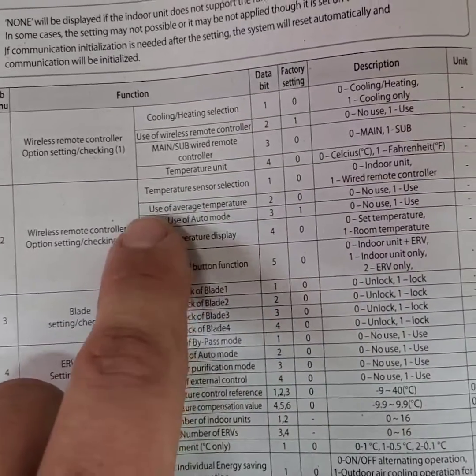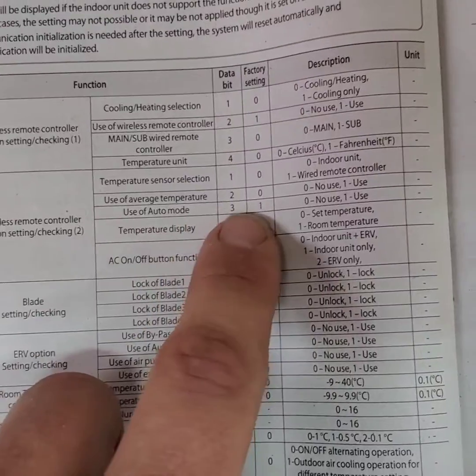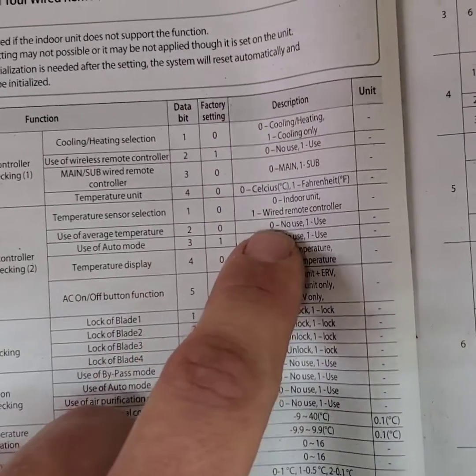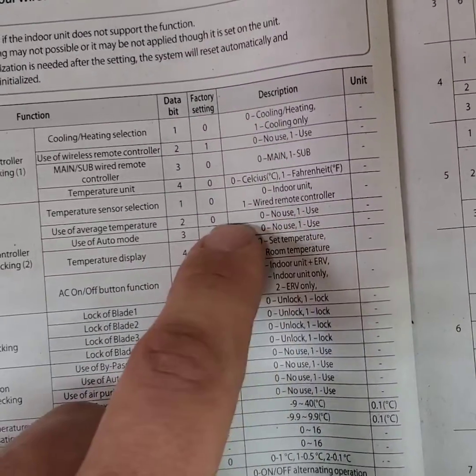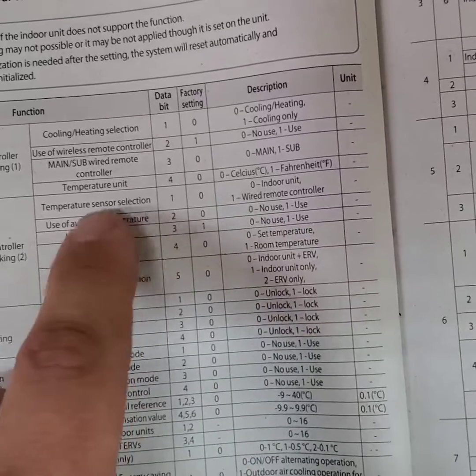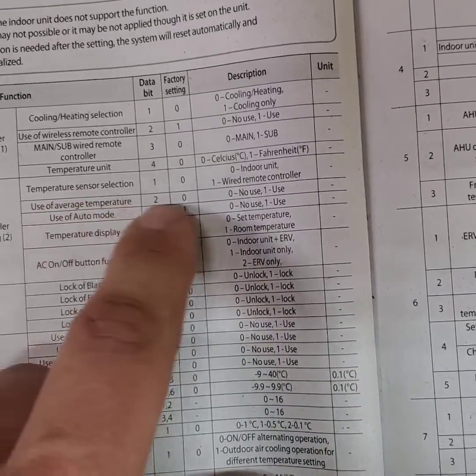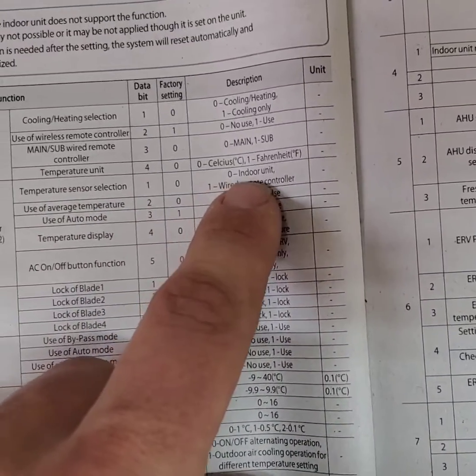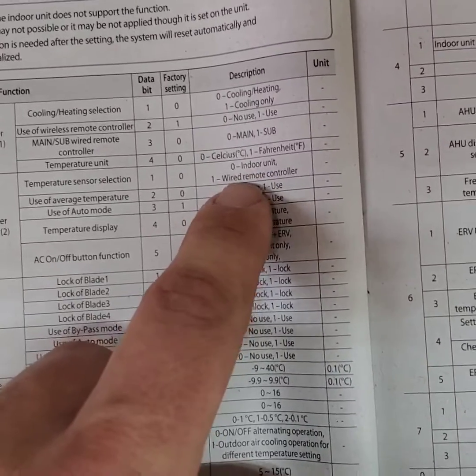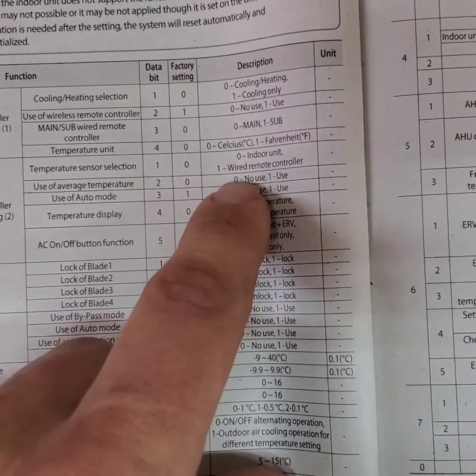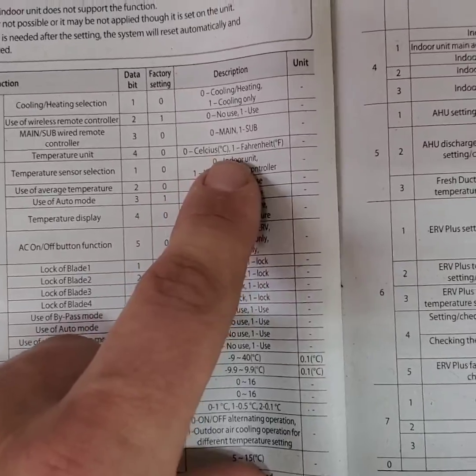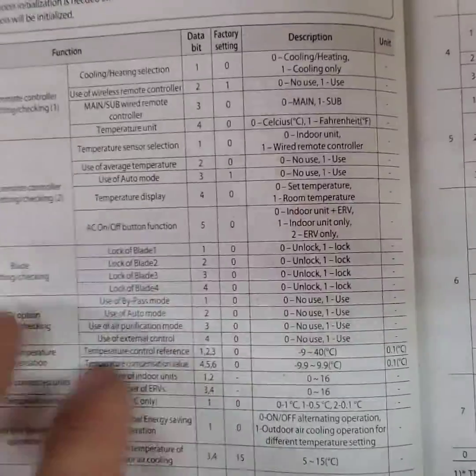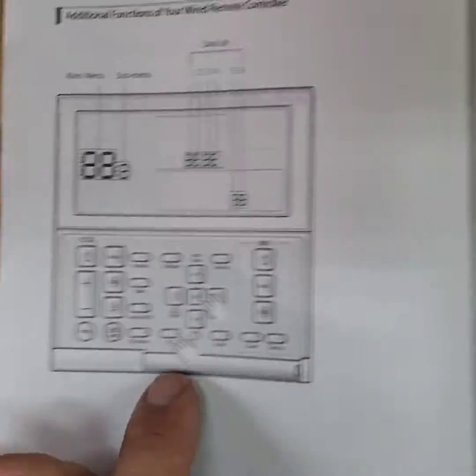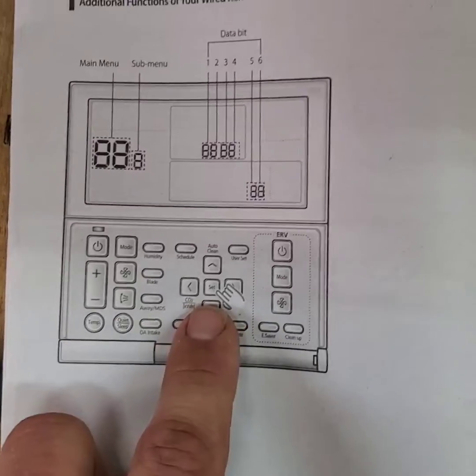Also check the use of average temperature setting, because this could be an issue. You want it set to either no use or use of average temperature; I usually set it to no use. For the temperature sensor selection, it depends on the application, the customer, and the needs, but usually I set it for the wired remote controller. Sometimes I have to set it for the indoor unit, but usually it's the wired remote controller. To get started with this, we push the exit and set buttons.